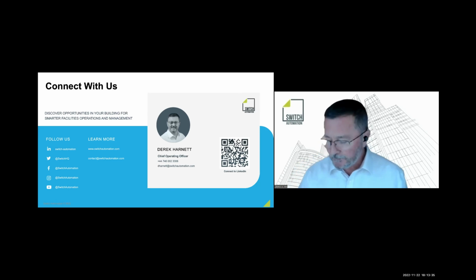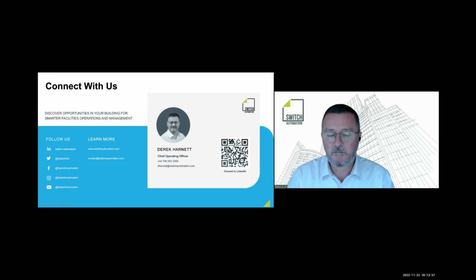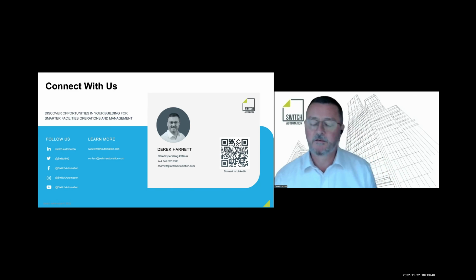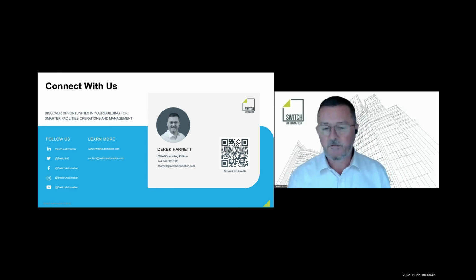If you say the onboarding process to scan the building takes 12 to 24 hours, depending on the size of the building, the number of data points, and the speed of the network, you can have an initial report within 48 hours on the digital readiness of the building. From there you start the ingestion and the mapping. If the protocols used within the building are open, such as BACnet, Modbus, or a direct MQTT or API call, then the ingestion of data is very fast.